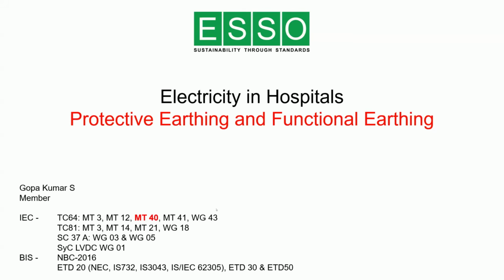So today we are going to discuss protective earthing and functional earthing. When we talk about the subject of earthing, first of all, we should understand that earthing is related to two important subjects in a hospital. Protective earthing, which is for safety of people and property against shock, against fire, against electrical equipment failure. And the second subject is functional earthing. Functional earthing ensures that all the electronic equipment are working properly, so that there is no communication lag between electronic equipment, and no problem for the electronic equipment during changeover from mains to the generator or so on. So these are two different subjects.